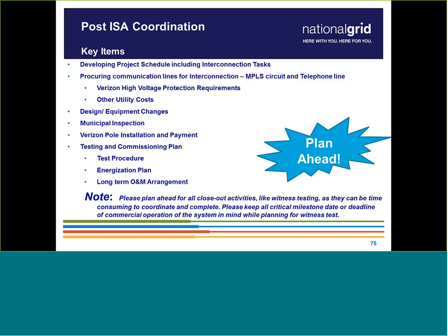So I can't clear it, no one will internally, until the wiring inspector calls and clears it. Sometimes I had issues where we went through a lot of coordination, recloser issues, and other unforeseen issues, and finally we're ready to go to the witness test. I brought everyone together to make it happen, and then we see that municipal inspection is still pending. So no one will do any work until that municipal inspection is cleared.